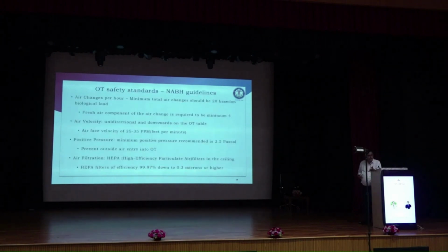There are OT safety standards, and the National Accrediting Board for Hospitals, NABH, has guidelines for our country - air changes have to be at least 20 per hour, and there has to be an air velocity which is unidirectional. Air comes in a laminar flow starting from the top, reaching the operation table, then moving away. This laminar flow is maintained so that infection rates are as low as possible. A positive pressure is kept in the OT so that no outside air enters - only inside air goes outside.